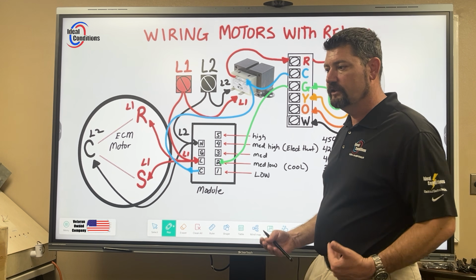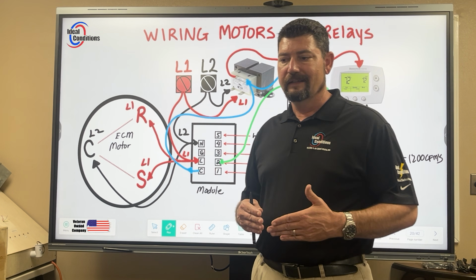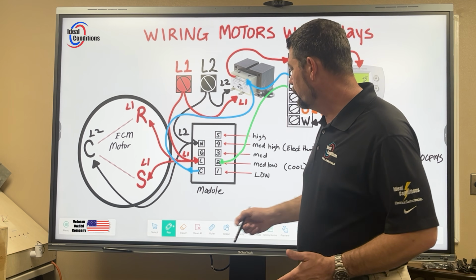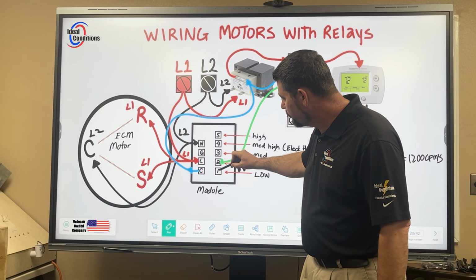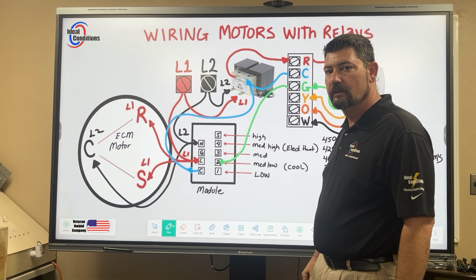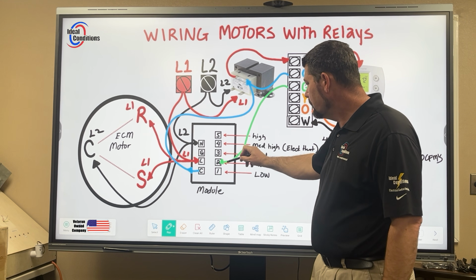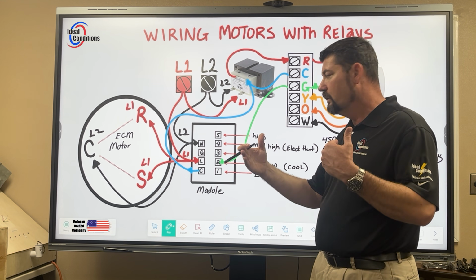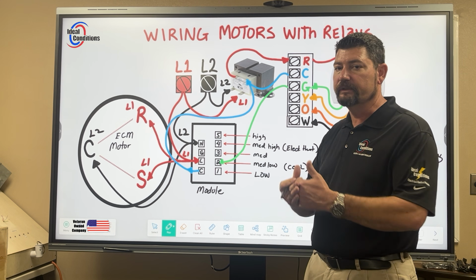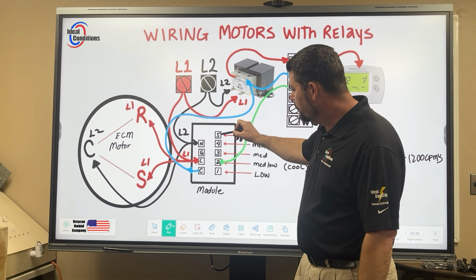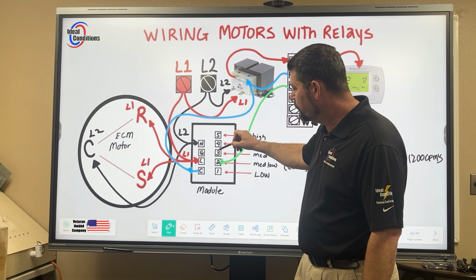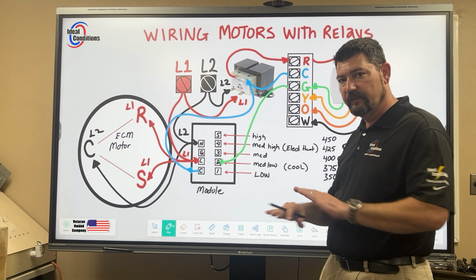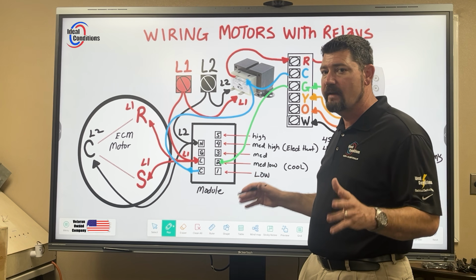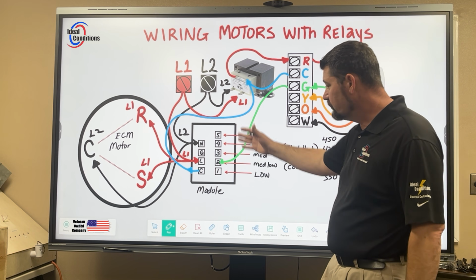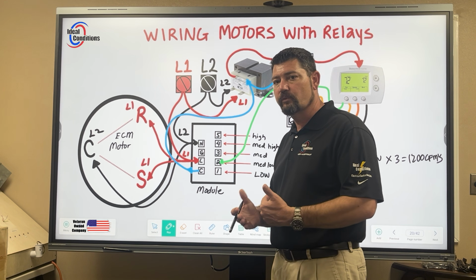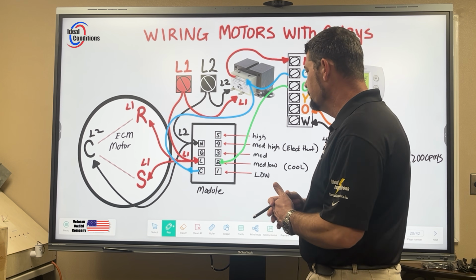Well, the first question you should be asking yourself is, how long did I remove 24 volts? And did I have 24 volts removed on all of these? Maybe I was getting 24 volts here and I shut the call for G off, and maybe the other one was being back-fed voltage somehow. If you can say that there's no 24 volts between 1, 2, 3, 4, or 5, and you know that it's been a minute and a half, 5 minutes, 10 minutes, a day, whatever, and it just won't shut off, then you have a relay that is sticking, okay? You have a relay that is sticking.